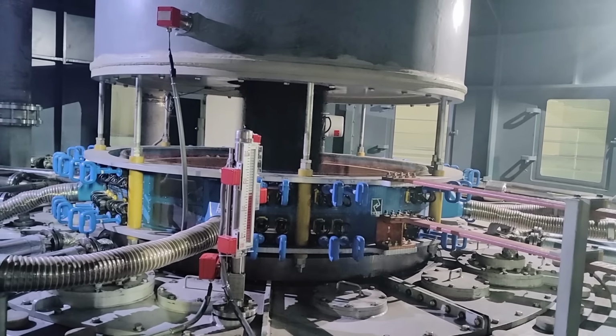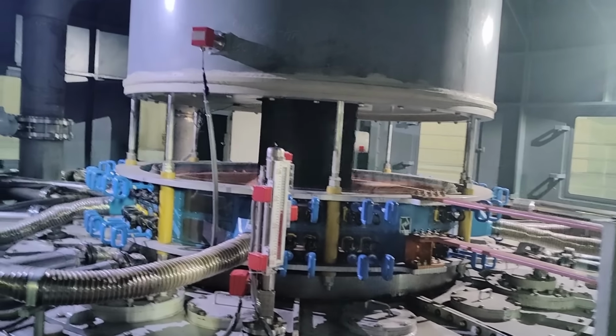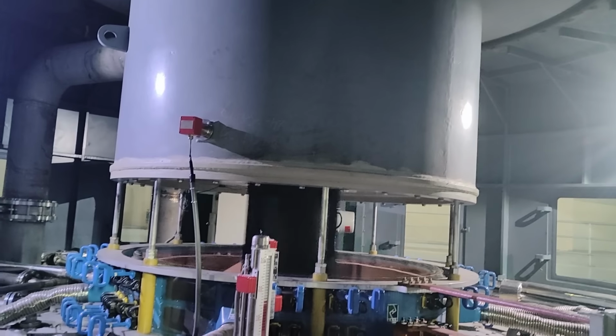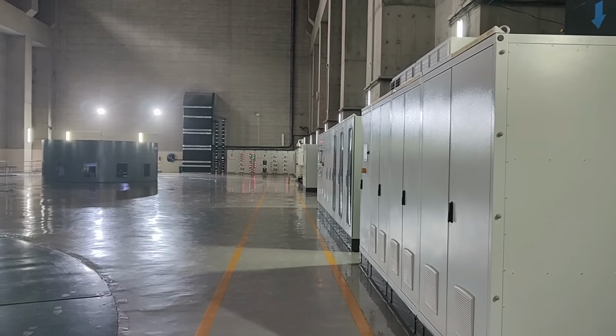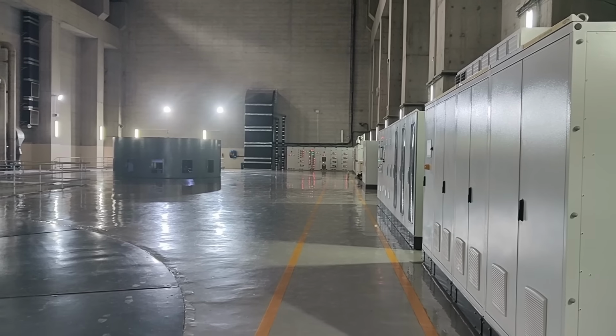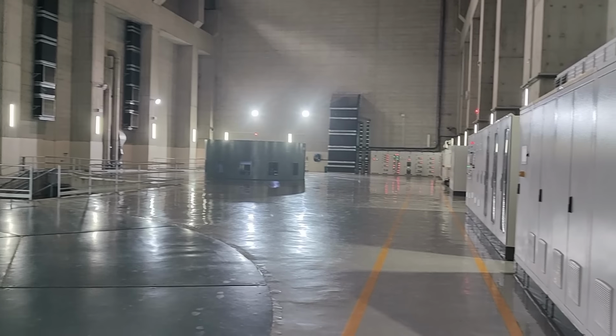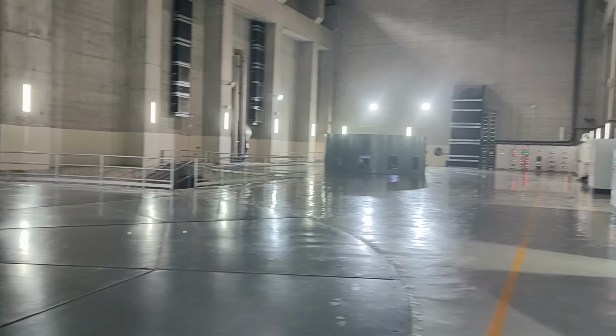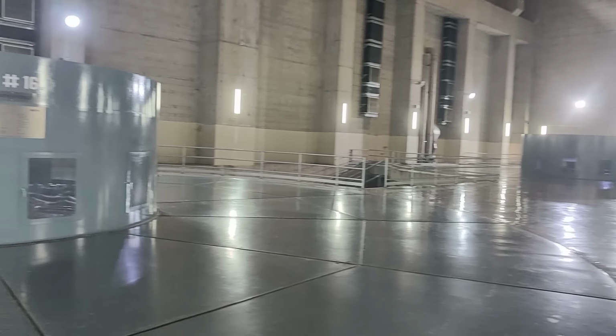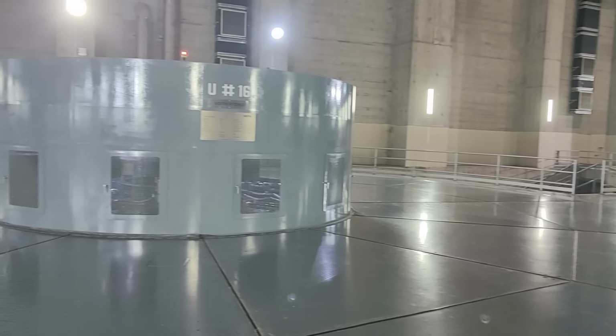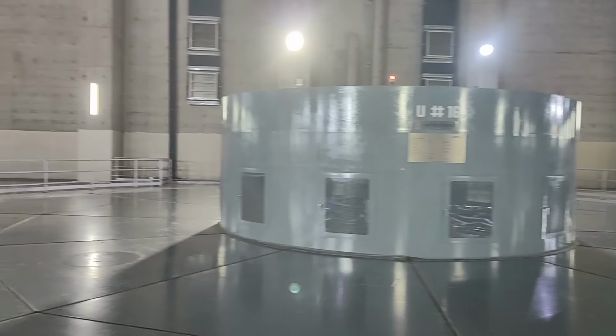And before you guys ask me in the comment section why only 20%, this opening is only to confirm that the pressure relief valve is working normally, and in case of an emergency this valve opens fully to release the high pressure. So every hydropower plant follows its own startup philosophy. Every machine has its own protection, interlocks and operating procedure.